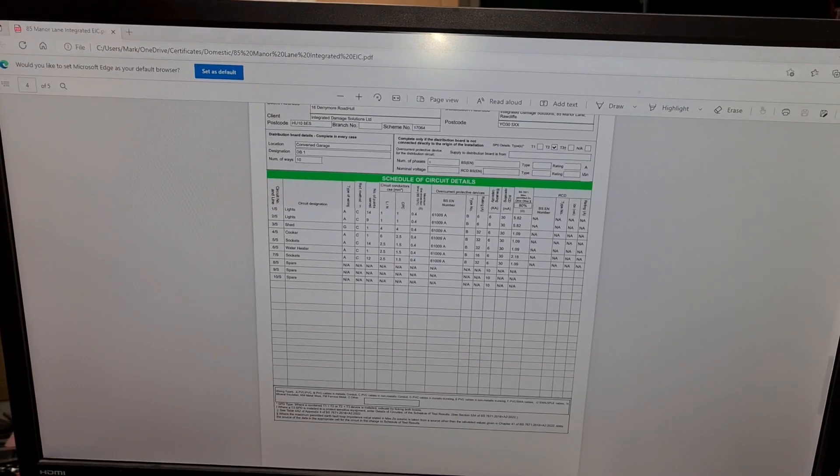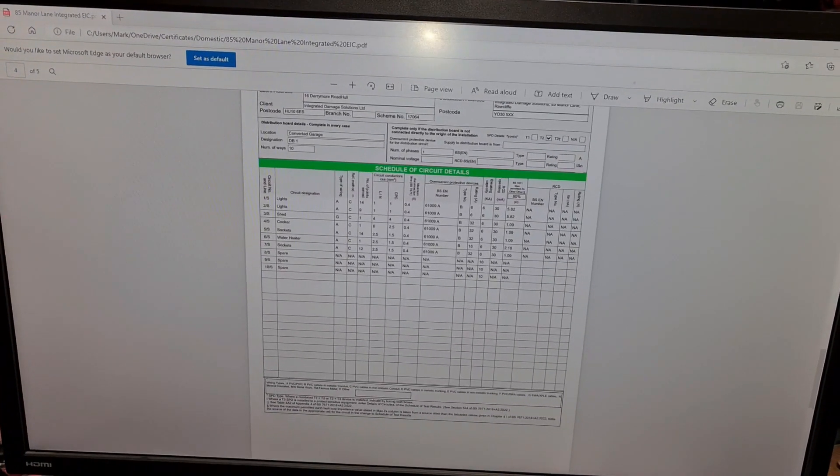You can see I'm producing the certificate now — I've actually nearly finished this one and I'm just checking it as a final check before I email it off to the client. Matthew did the wiring centre and said there were no real issues. It was a Vaillant one, really simple to set up — a straight swap, but with the added difficulty of having to move its location. Apparently they'd updated the connectors from the first version to the one we fitted, so all those had to be rewired as well. Thank you for watching — let me know what you think in the comments, give it a thumbs up or down, and we'll see you on the next one.